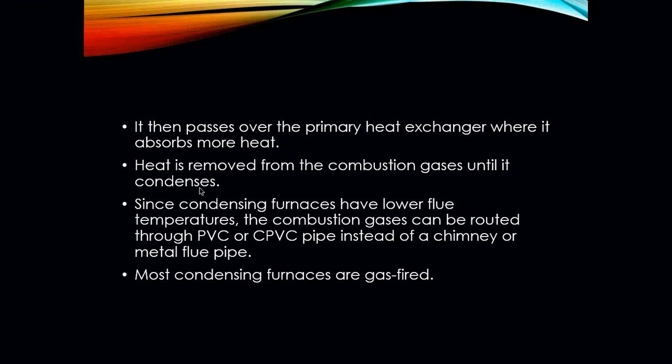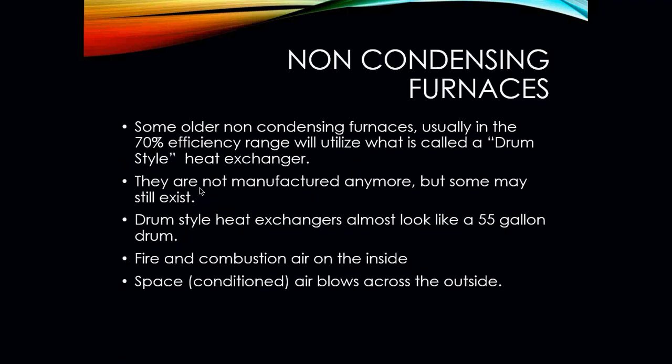Since condensing furnaces have lower flue temperatures, we can use PVC or CPVC to vent the gases out instead of a chimney, metal flue pipe, or however the construction is set up. Most 95% furnaces are not installed through a chimney — they have their own point of exit in a home, either through a roof or through the side of a building. Most condensing furnaces are gas-fired; there really are no oil-fired condensing furnaces at this point.